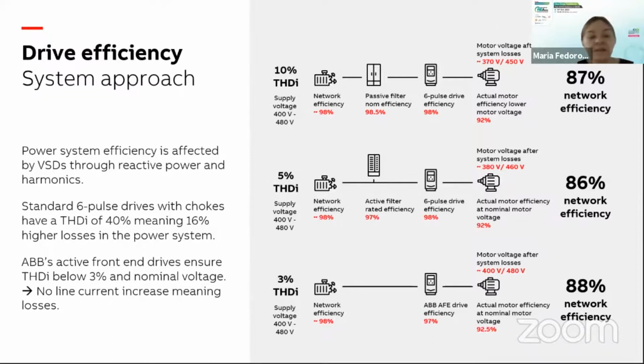We've been seeing that very often consultants select drives based on drive efficiency. But keep in mind that certain drive technologies bring a positive effect for the applications they control. However, if the effect on power quality of the drives you choose is negative, in terms of electromagnetic noise introduced to the power network, this can affect the power network efficiency negatively. When selecting drive technologies, look at how they perform in terms of power quality.